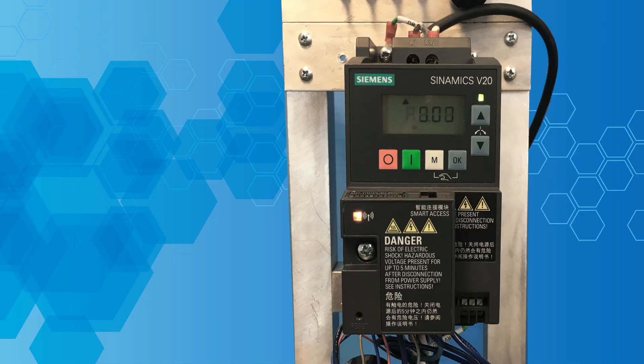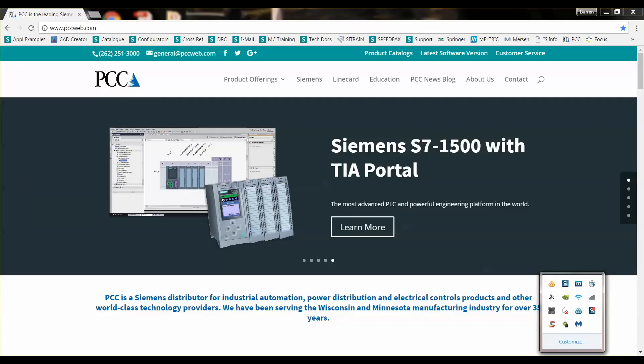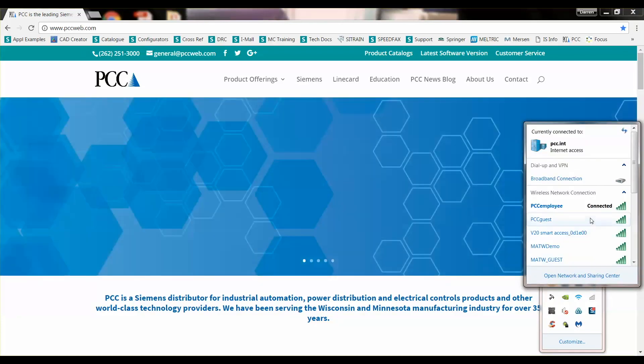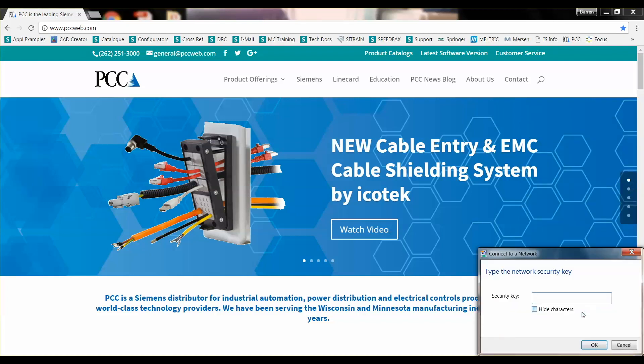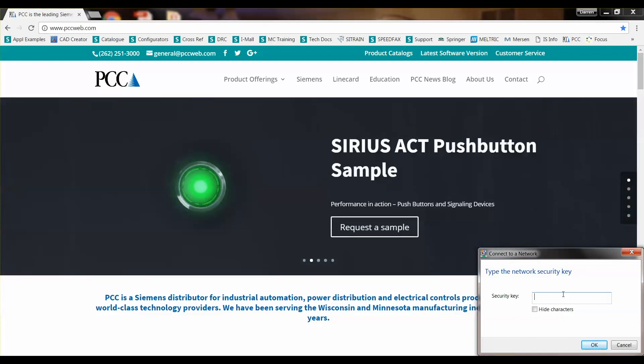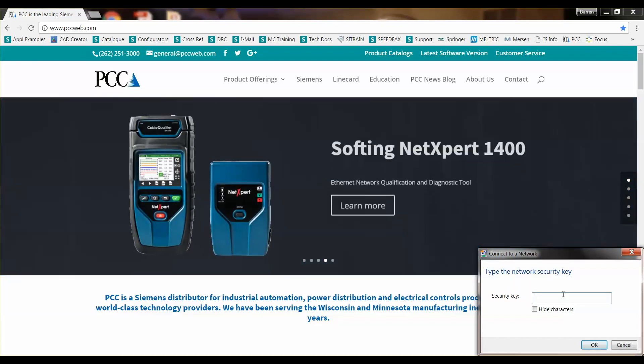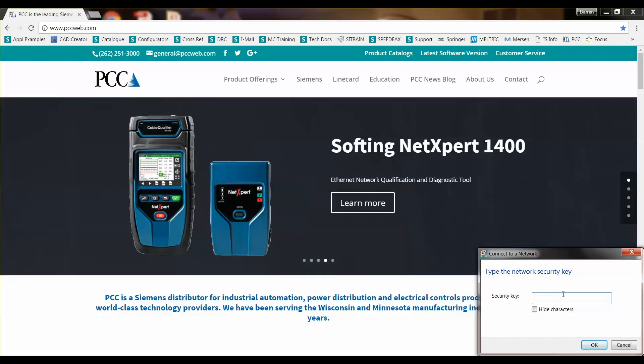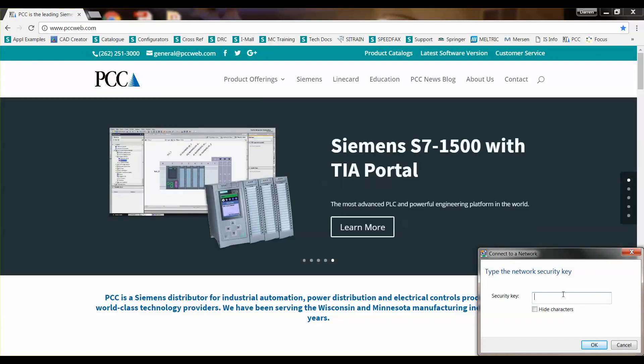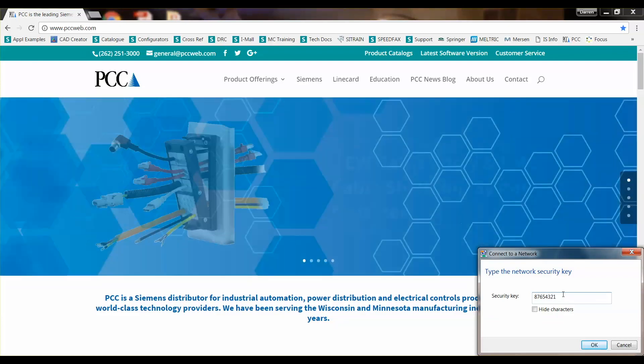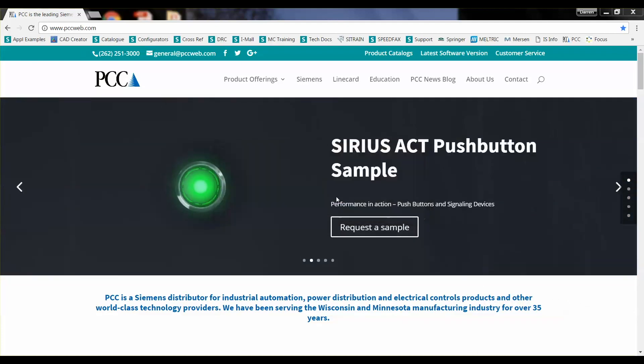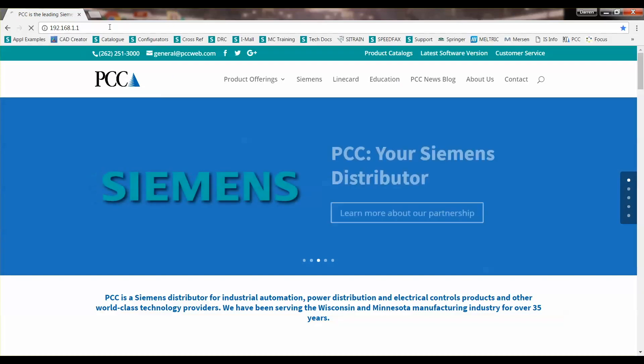Then turn the power on and when it boots up there will be a solid orange light. You can go to your laptop or mobile device and connect to the V20 Smart Access Module hotspot. It's going to ask for a password. The default password is 12345678. When you enter that, you go to the web page for the Smart Access Module which is 192.168.1.1 and it will ask you to change the password from the default. I've already done that so my password is 87654321. The light on the front of my Smart Access Module has turned solid green indicating that I'm connected. So I'll go to the web page 192.168.1.1.